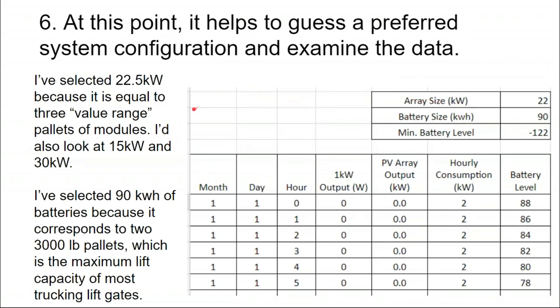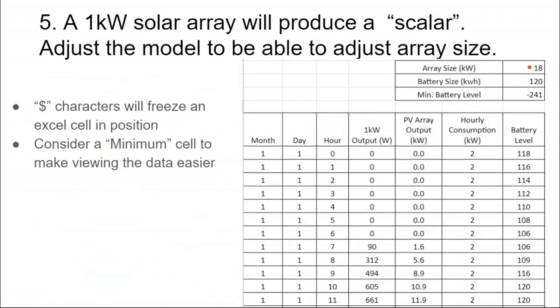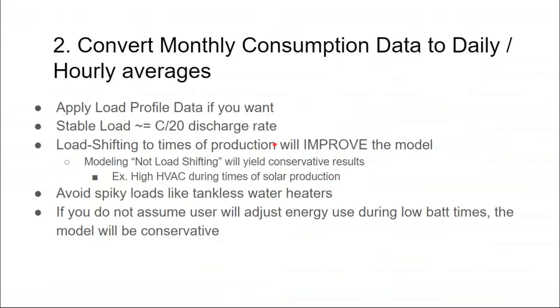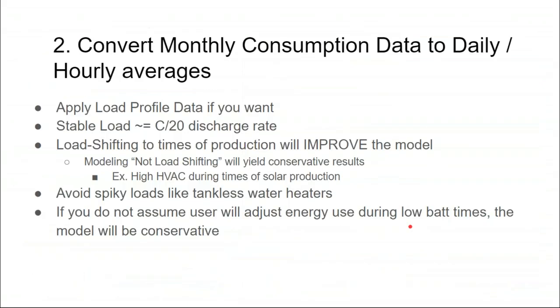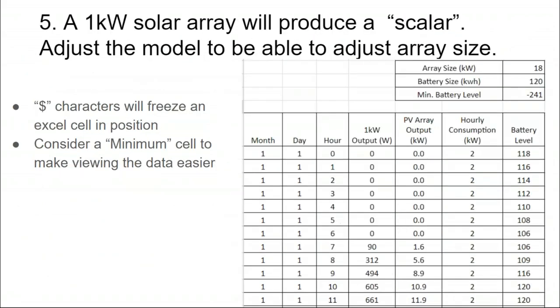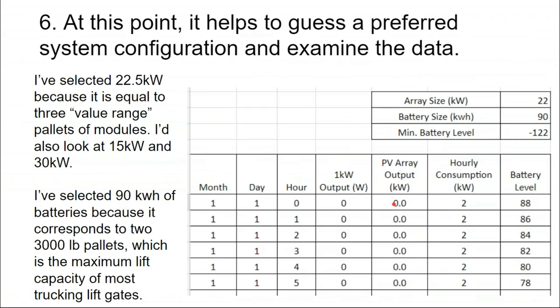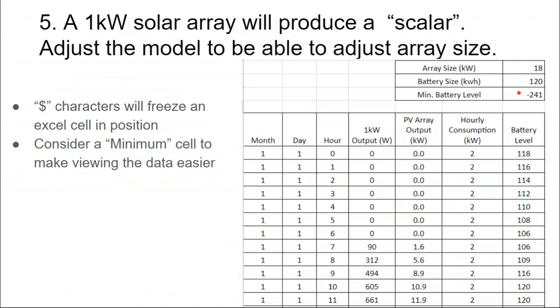Then I go and say, okay, maybe an 18 kilowatt array is actually too small. It helps to have a nice visual chart, such as what Energy Toolbase makes, but you can create these same charts in spreadsheets if you choose. Being able to quickly and visually assess when I got down to that 241 bottom limit, and was that a summer day where I have high electrical loads and not a lot of sunshine, or was it a winter day where I have even less sunshine, and what do my loads look like then, and how do I recover out of it, and would that benefit from an increased array size?